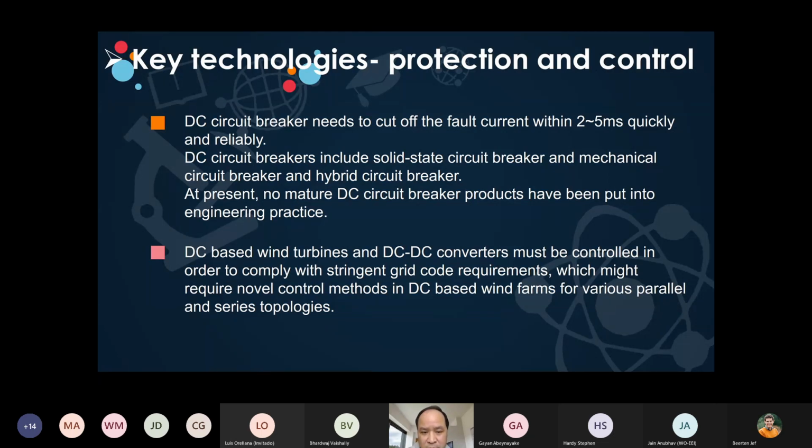But for medium voltage, is this still the case? If we use mechanical, some of the mechanical methods may be slower to generate this current zero, but can this be acceptable? Or we use the pure solid state circuit breaker, or even some other medium voltage one. Some are already available from the manufacturer. Can we accept that kind of power losses? Because the voltage is not 400 kilovolts, it's only 40 kilovolts, so it's 10 times fewer IGBTs or whatever solid state components. So that's also something we need to compare.